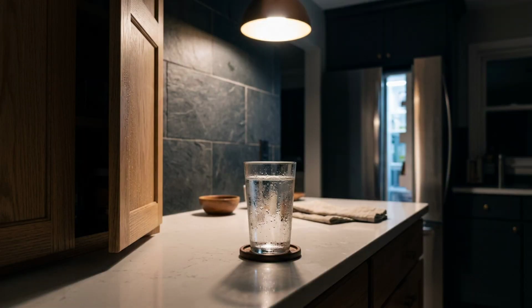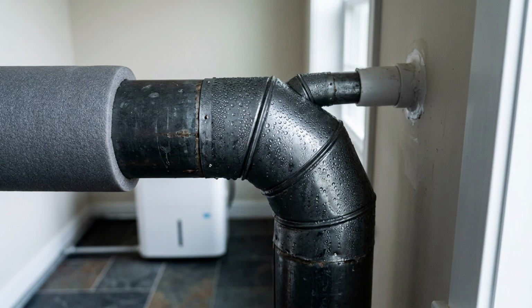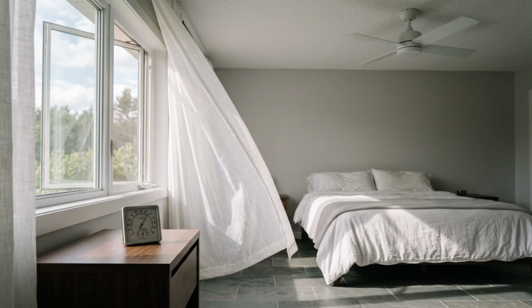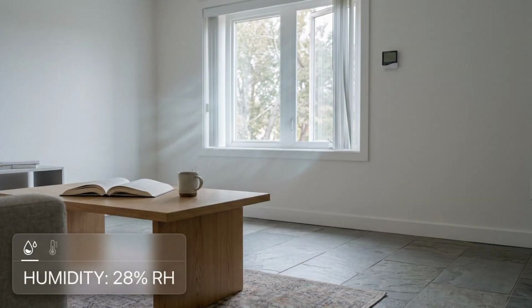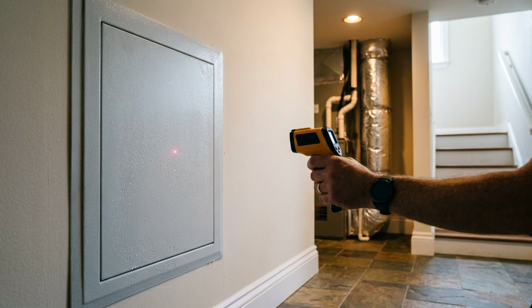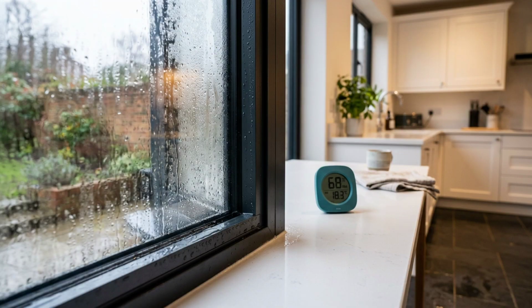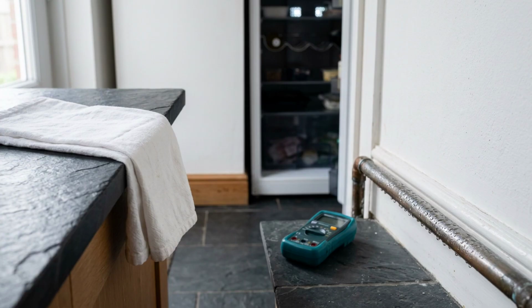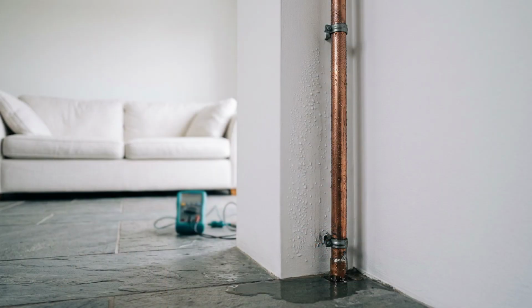Now check the surfaces. Condensation occurs when humid air reaches a surface at or below the air's dew point. EPA's Technical Moisture Guide gives a useful relationship. At 50% relative humidity, a surface around 20 degrees Fahrenheit cooler than the room air can reach condensation conditions. That can happen at a cold window, an uninsulated pipe, an exterior wall corner, behind furniture with little air movement, or on cold HVAC components.